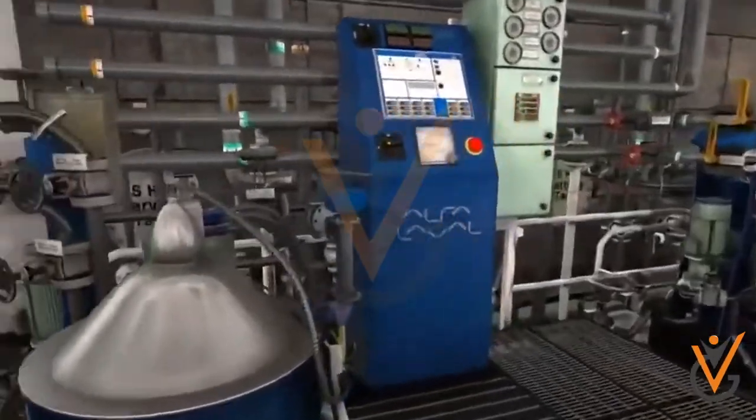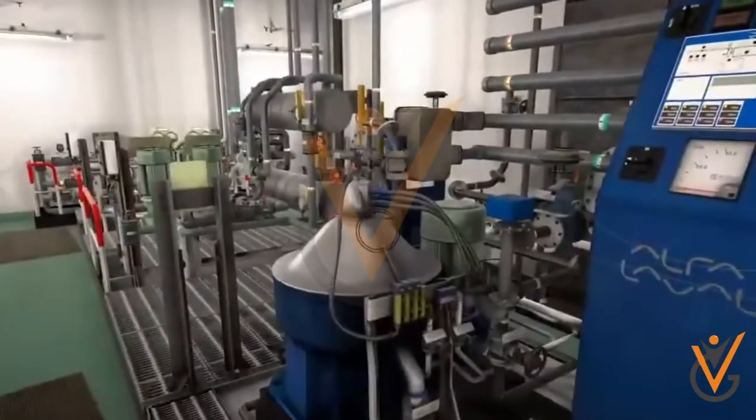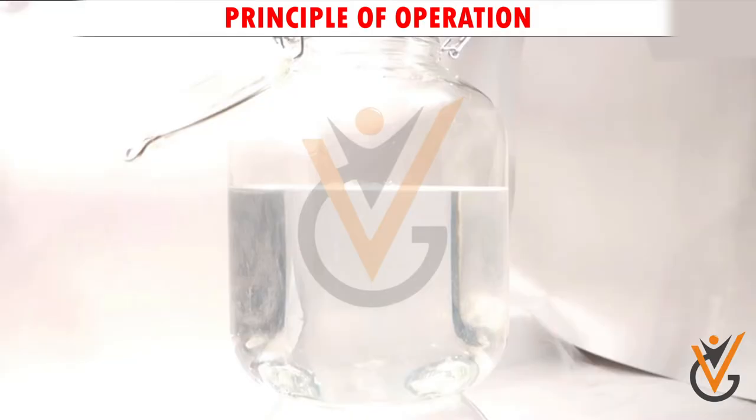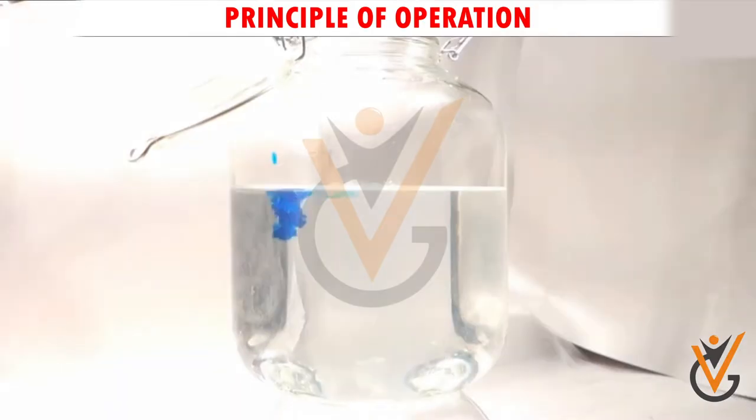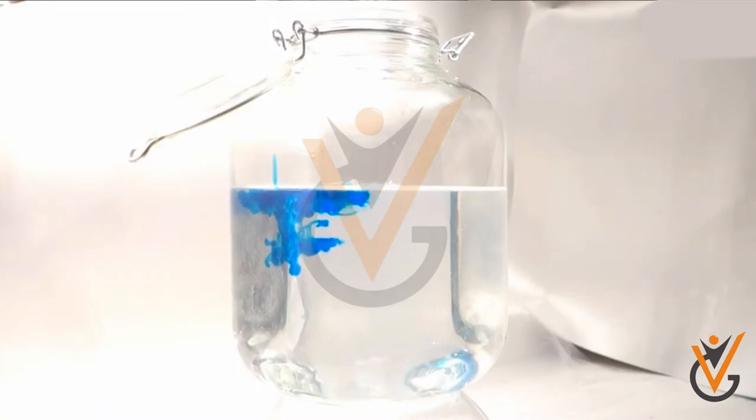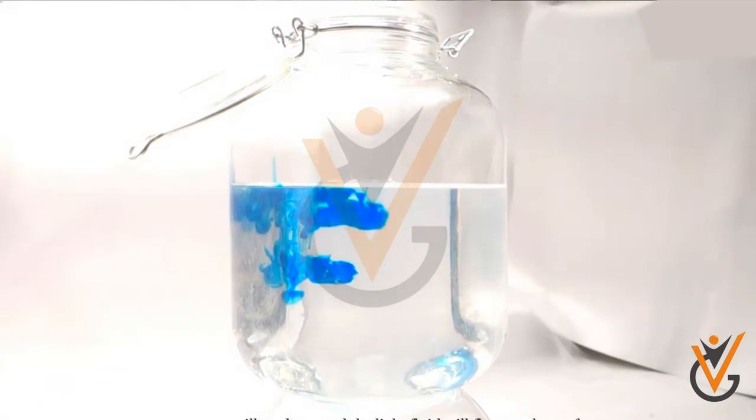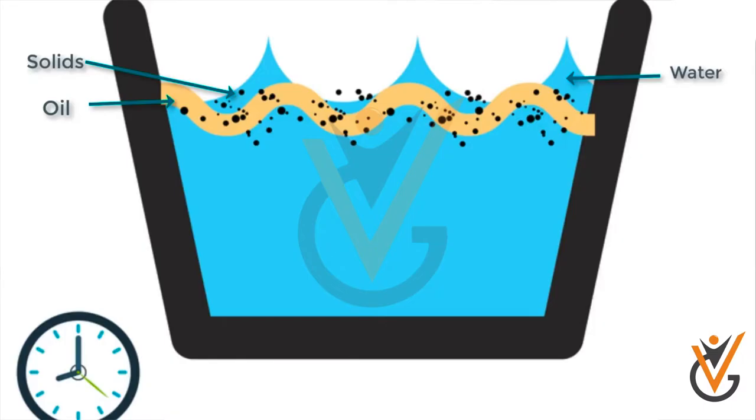Let us see in detail about working principle and construction of purifier used on board ship. Principle of operation: Oil, water and other impurities are of different density. Whenever the oil is subjected to centrifugal force, heavier particles - water and solid - will be thrown outside, and lighter particles will remain close to the center.